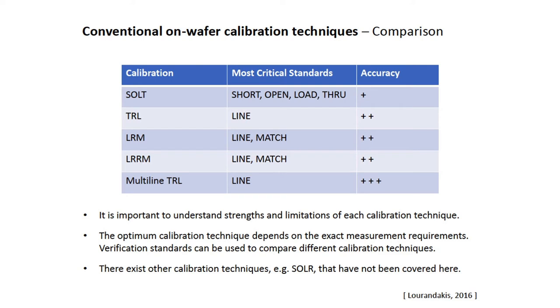Multi-line TRL involves multiple lines used across all frequencies; the varying weights solve the problem of band breaks in conventional TRL. It allows very high-performance calibration of on-wafer standards and has been established as a reference calibration technique for metrology at NPL. However, the downside is it needs large space, and sometimes space is very expensive. This table summarizes these calibration techniques: multi-line TRL provides the highest accuracy with the most critical standard being the line; TRL gives reasonably accurate calibration; for LRM you need to know line and match standards well; and for SOLT you need to know all standards very well.